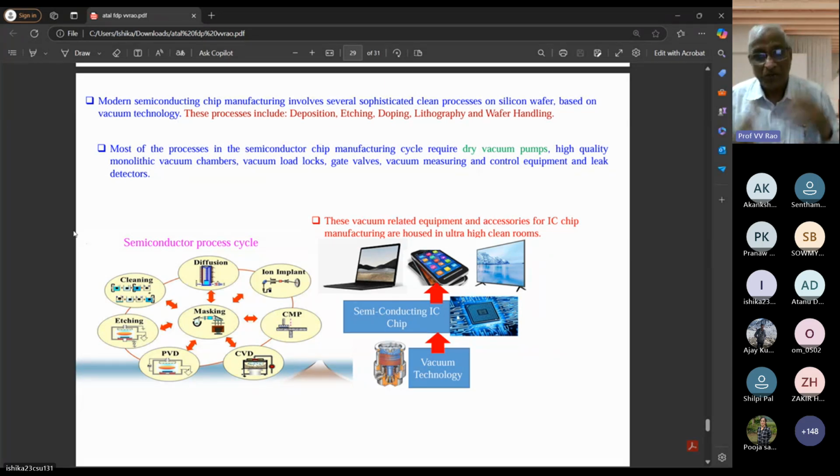You can certainly do that. When you do all the proper valves, because simply connecting a valve in a water pipe is also required. But these valves are high vacuum compatible valves. The chambers are high vacuum compatible. Whatever processes are going on, all those interconnecting links have to be properly conducting. And the surface smoothness of the chambers is very important. And whatever is inside the chamber, the manipulator, because after all you have to connect this fellow to that fellow, also should be polished properly.